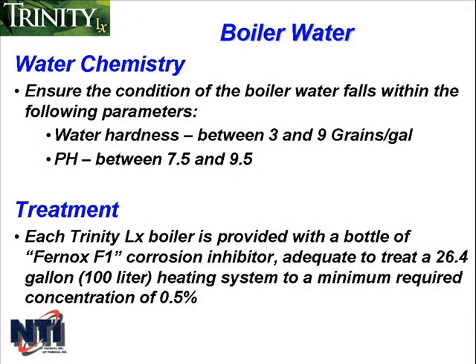When installing the Trinity Lx boiler, you need to consider the condition of the water in the heating system. The hardness should be somewhere between 3 and 9 grains per gallon, and the pH should be between 7.5 and 9.5. Boiler water that falls outside of those conditions needs to be treated with a corrosion inhibitor, but there really is no downside to treating the water even when it falls within those ranges.